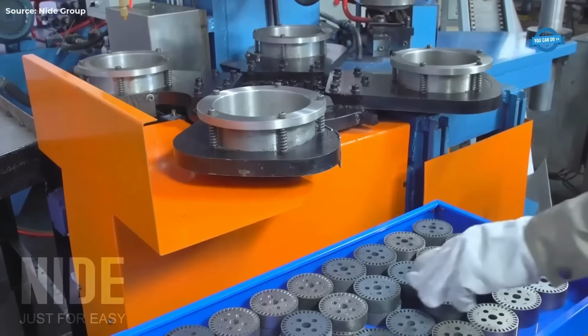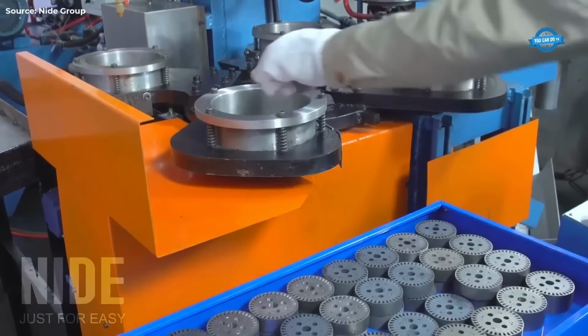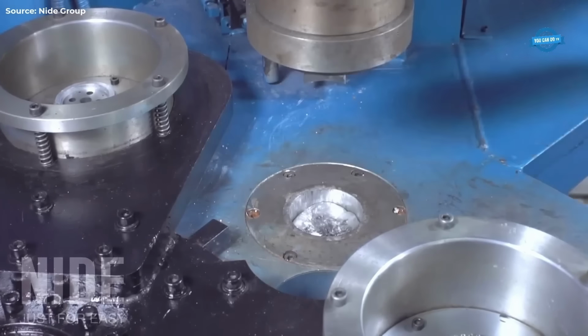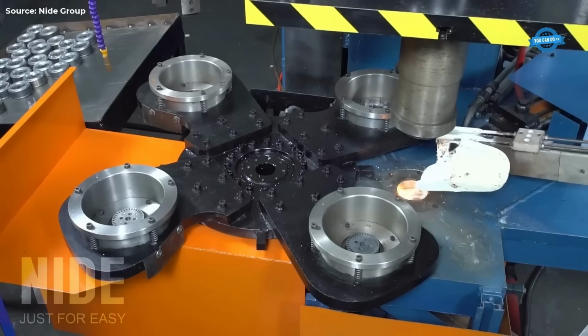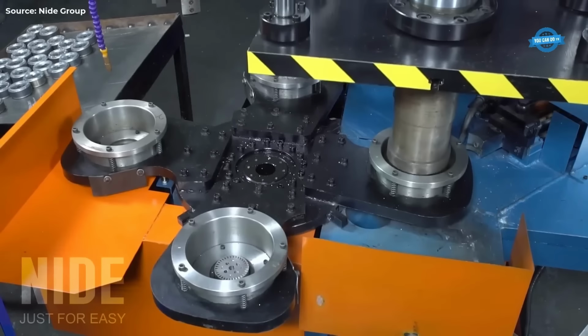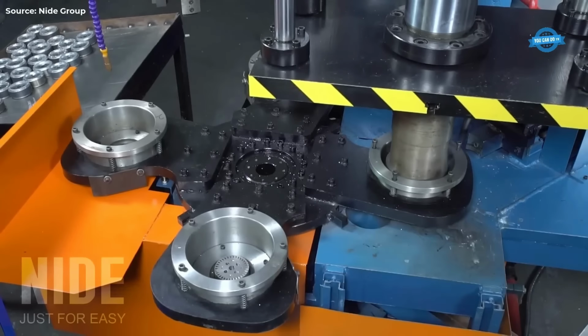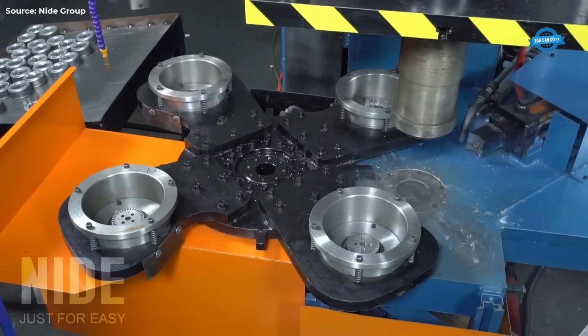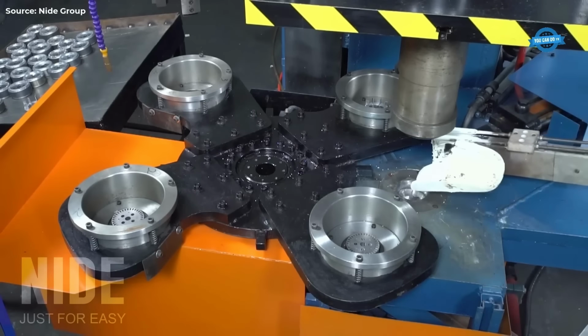The rotor die casting machine features 4 working stations, automating the process of loading aluminum melt into the tooling. Controlled by a PLC system, it supports 3 injection modes: slow, fast, and secondary. The fast injection flow can be manually adjusted. Equipped with an automatic feeding system, cutting device, and mold unloading mechanism, the machine ensures seamless production. It includes protective pneumatic doors on all sides for operator safety and a water cooling system for consistent operation.